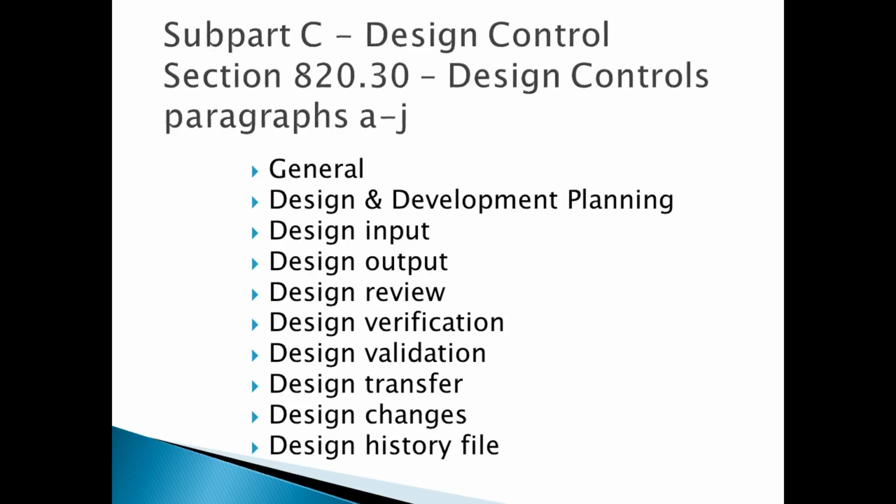Design verification are the test protocols that they develop to ensure that the design output is meeting the design input, and those are typically bench tests. We do not get involved with design validation because quite often those are very expensive biocompatibility tests, animal testing, human clinical testing, but we teach them about that. It's just not something we do in our design course. Design transfer is moving the design from a design and development environment into a production environment, and that's also something that we address but we don't do in our course.